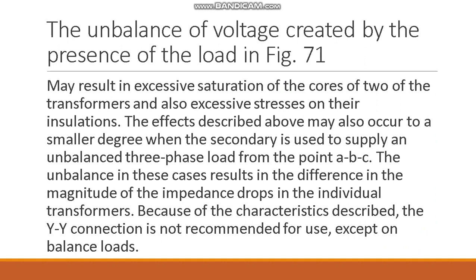These changes in phase voltage cause the neutral 0 and N to rove, and in so doing the voltage on the load is reduced. Such a circuit will not supply a sizable load between the secondary neutral and one line. The unbalanced voltage created by the presence of the load in Figure 71 may cause excessive saturation of the cores of the two transformers and also excessive stresses on their insulations. Because of these characteristics, the Y-Y connection is not recommended for use except on balanced loads.